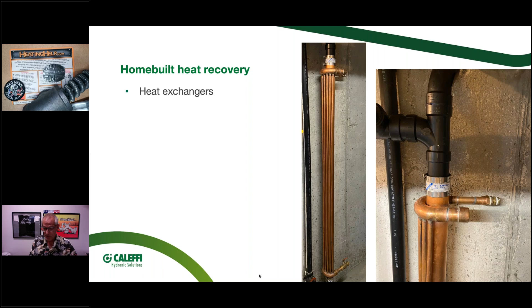So yeah, I'll let you know how this works. I think it's going to do something. I don't think it'll be as efficient as some of those store-bought ones where they've got a lot better tubing contact and a lot better surface area, but this is why it's important. If you want to know that information, I could guesstimate what's going on, or I'm going to put one of the Caleffi BTU meters. So basically, here's a picture of one installed on a job. If I know the flow rate going through there, and I've got 2 temperature sensors measuring my delta T across it, really that's the information I need to come up with a BTU performance or output on that. So that's really the best way to know exactly what's happening.